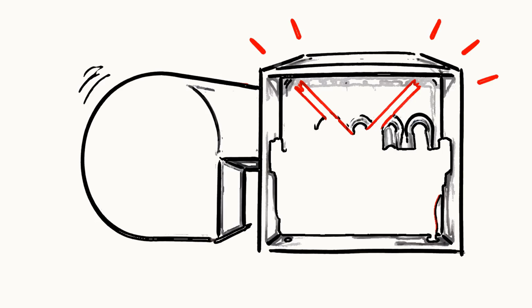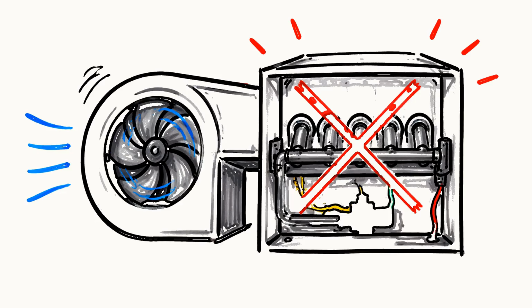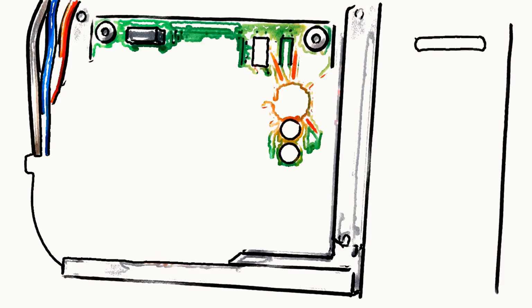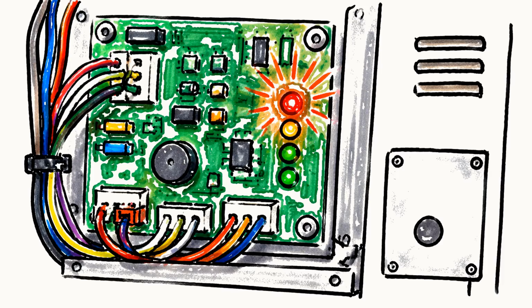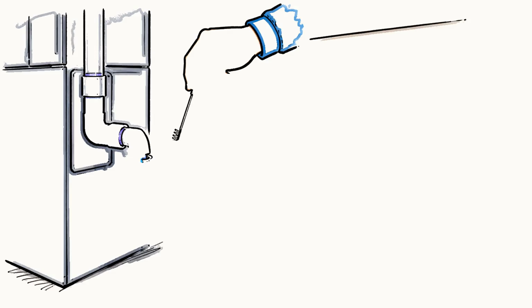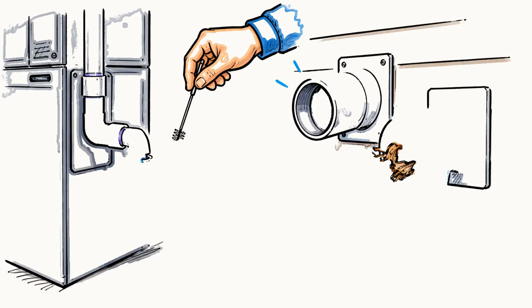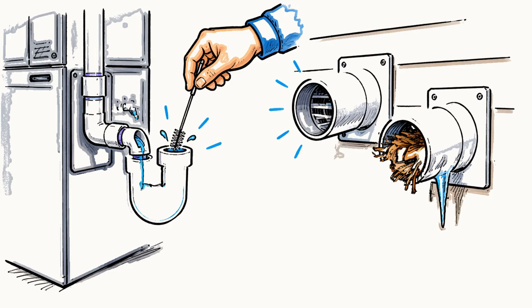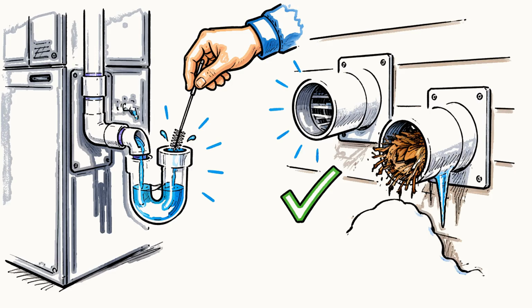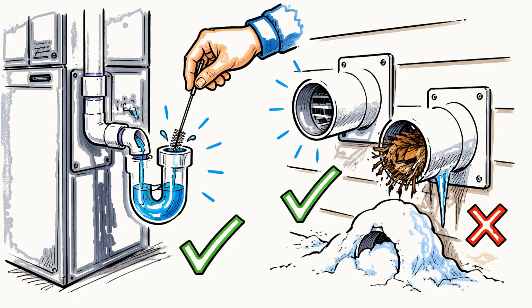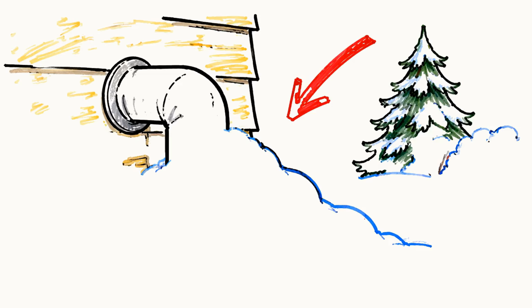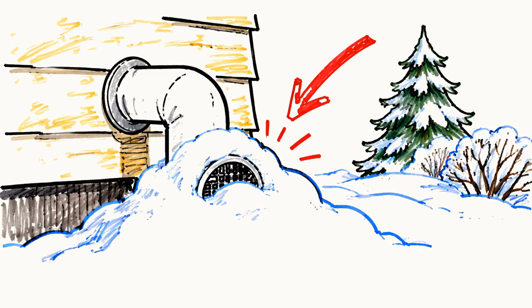The clue is that you hear the draft fan running, but the burners never fire, often with a blinking error light on the control board. Clearing the condensate drain line and trap and making sure the intake and exhaust pipes outside are not blocked by snow, ice, or a bird nest will often bring it right back. That outside pipe getting buried in snow is a classic midwinter no heat call.